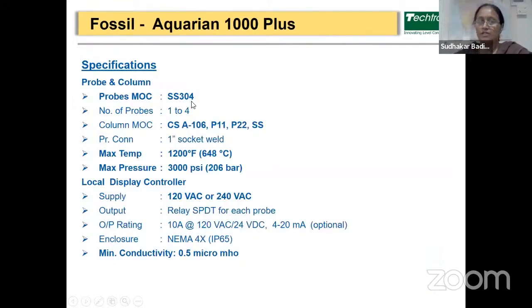The probe MOC is SS304. Number of probes will be 1 to 4. The column MOC is CSA106, P11, P22, or SS. Suitable for maximum temperature up to 1200 degrees Fahrenheit and maximum pressure up to 3000 PSI. Then the controller supply will be 120 volt AC or 240 volt AC, and you will get the relay output of SPDT contacts, which are suitable for 10 ampere, 120 volt AC or 24 volt DC. Optionally, you will also get 4 to 20 milliampere output. The minimum conductivity is 0.5 micromho.